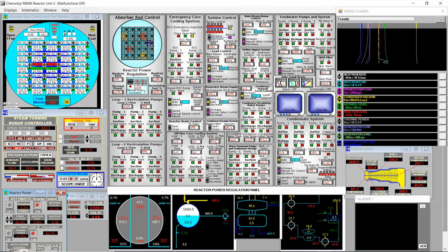And the vibration now is at 50%, not very low, but still fine. This is probably because of this. We have a bit of differential expansion even if we are not in the red line, and this creates some vibration. But anyway, we'll continue increasing power. We go to 50% now.